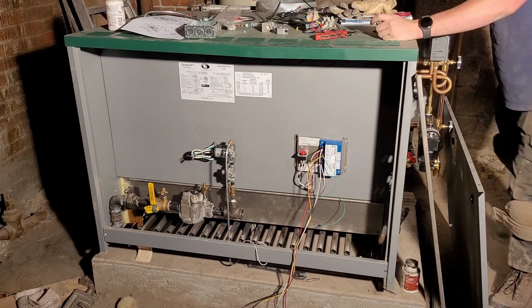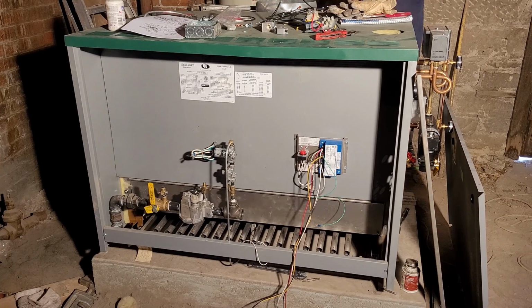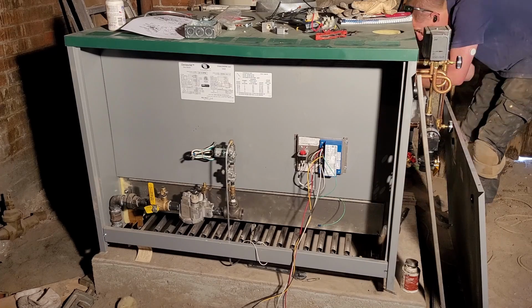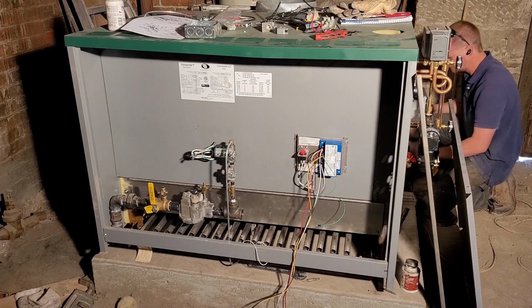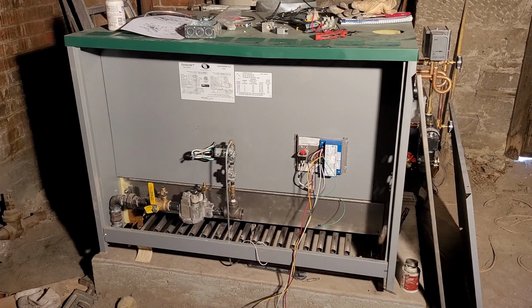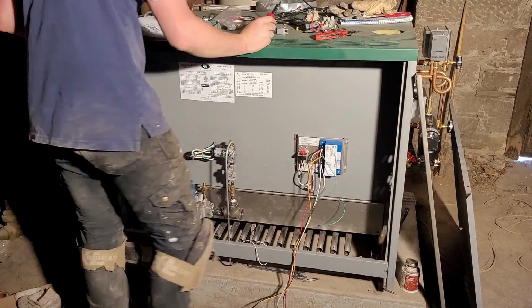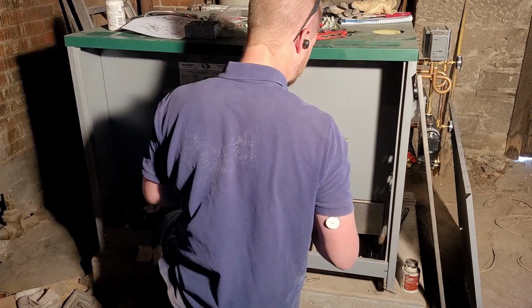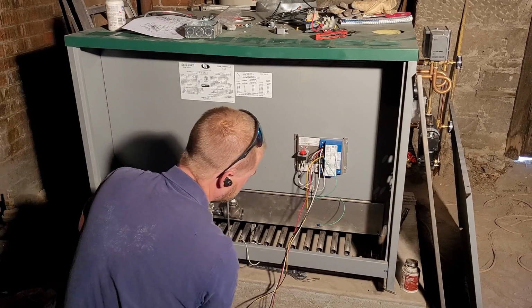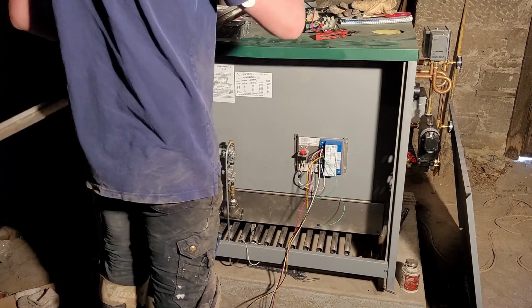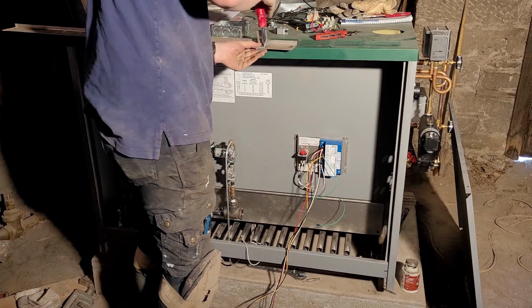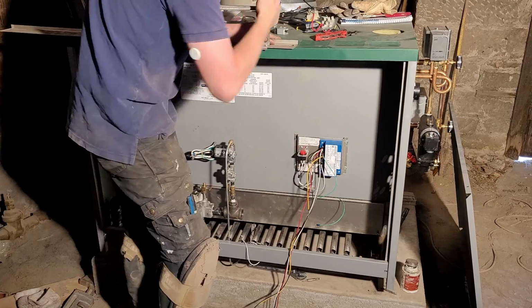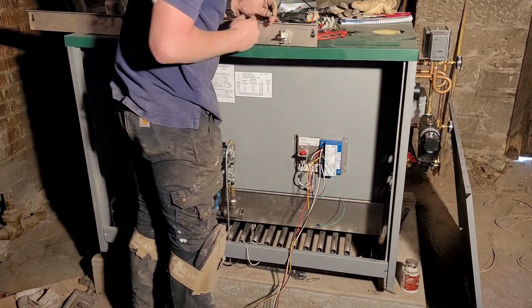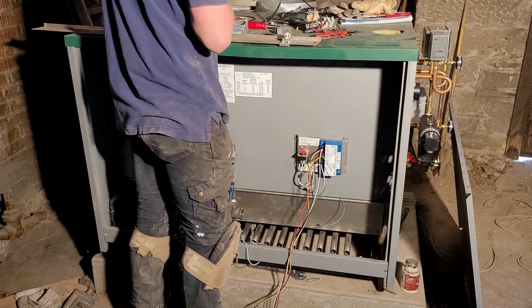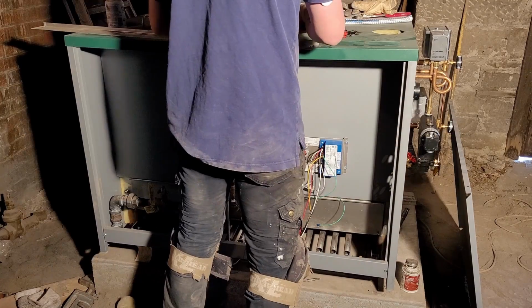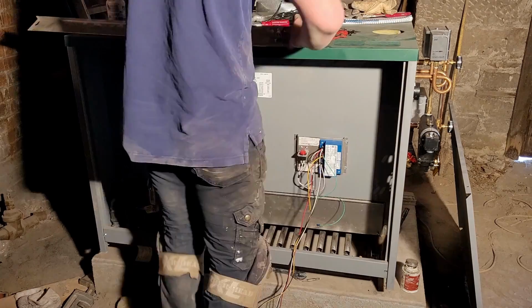So what these controls do is they pass a very high voltage, but incredibly small current through the pilot flame to the ionization probe. When the control senses that that current is flowing through the pilot flame, then it says, there must be a flame there. So it sends power to the main burners, and the burners fire. The instant that the pilot flame goes out, for any reason, it's like flipping a switch. Now there is no ionized path for that current to travel through, so it will turn off immediately. So it's considered a much safer approach to pilot safety than a thermocouple is. So that's the modern standard.